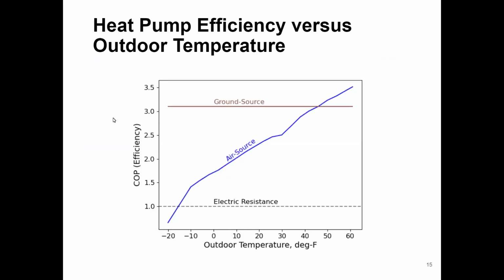All of which is to set you up for this graph, which I want you to understand. A ground source heat pump, because it's drawing from the ground or a body of water, doesn't lose performance as the temperature goes down, because the temperature of that source stays consistent all the time. An air source heat pump will reduce in efficiency as the outdoor temperature goes down. And for contrast, electric resistance—a space heater or something like that—always has a coefficient of performance of 1. For every unit of electricity you put into it, you get 1 out.